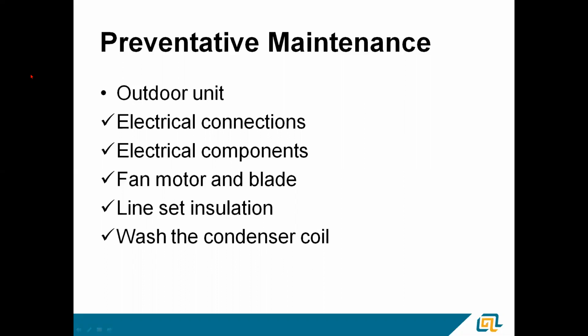Line set insulation, we've all seen it where the line set insulation is just about totally off of that line set. It's a really good idea. Check it over. If it needs some insulation added to it, add it, because that's going to affect your superheat at the compressor. And of course, superheat, that's the compressor's number one enemy, if it's not correct. Wash the condenser coil. Take a good look at it. You know, Trane American Standard product, that's a fine fin coil. It's a little bit more difficult to clean, but by the same token, I don't think it loads up anywhere near as bad as a fin and tube coil does.